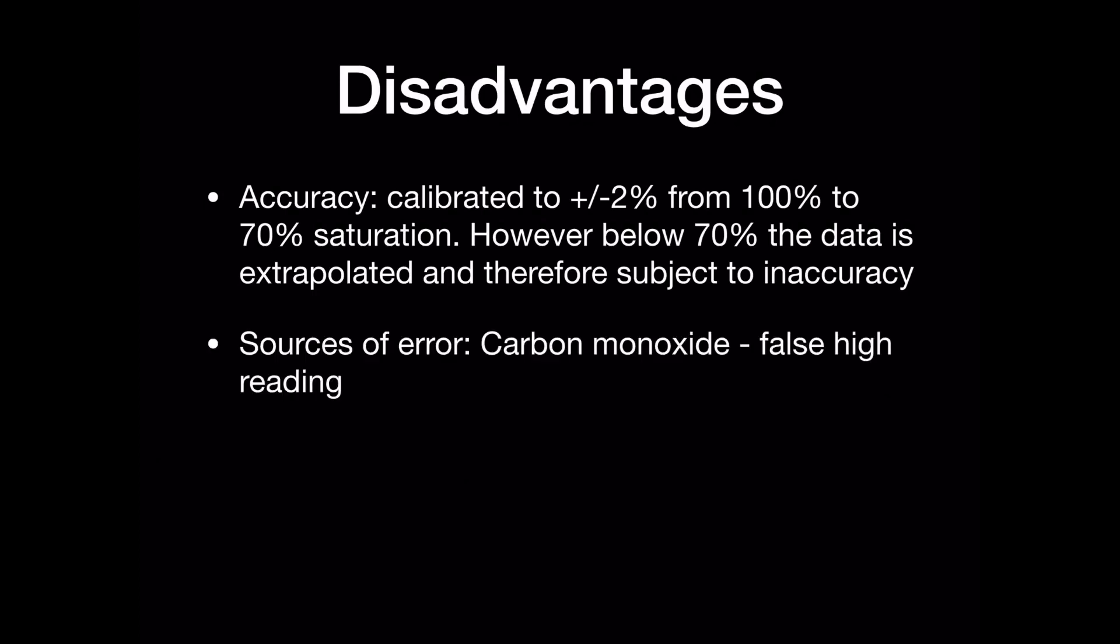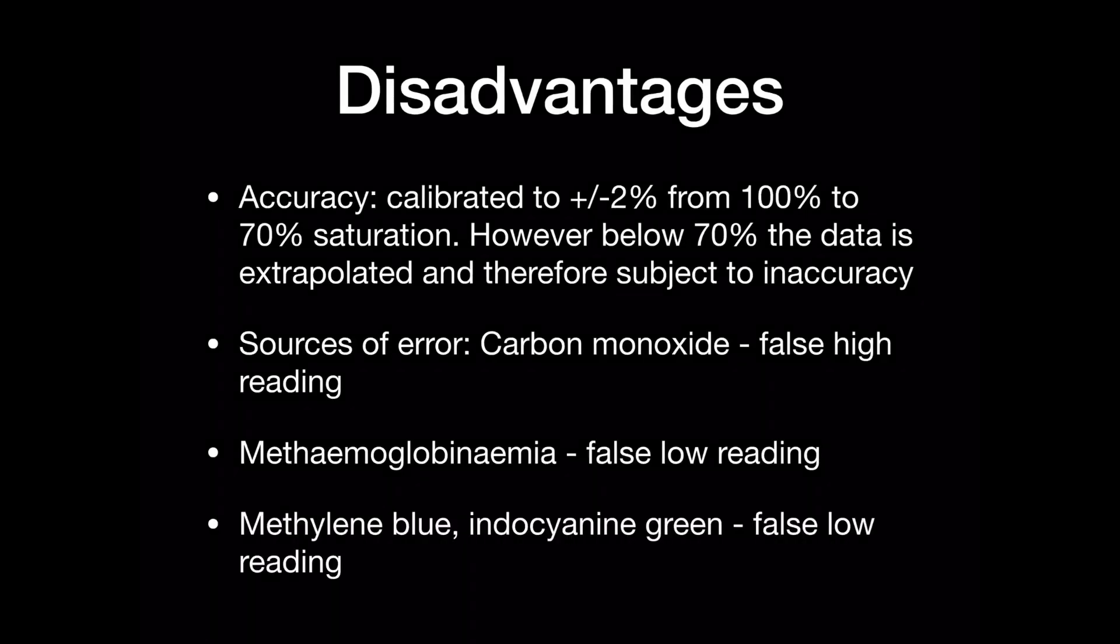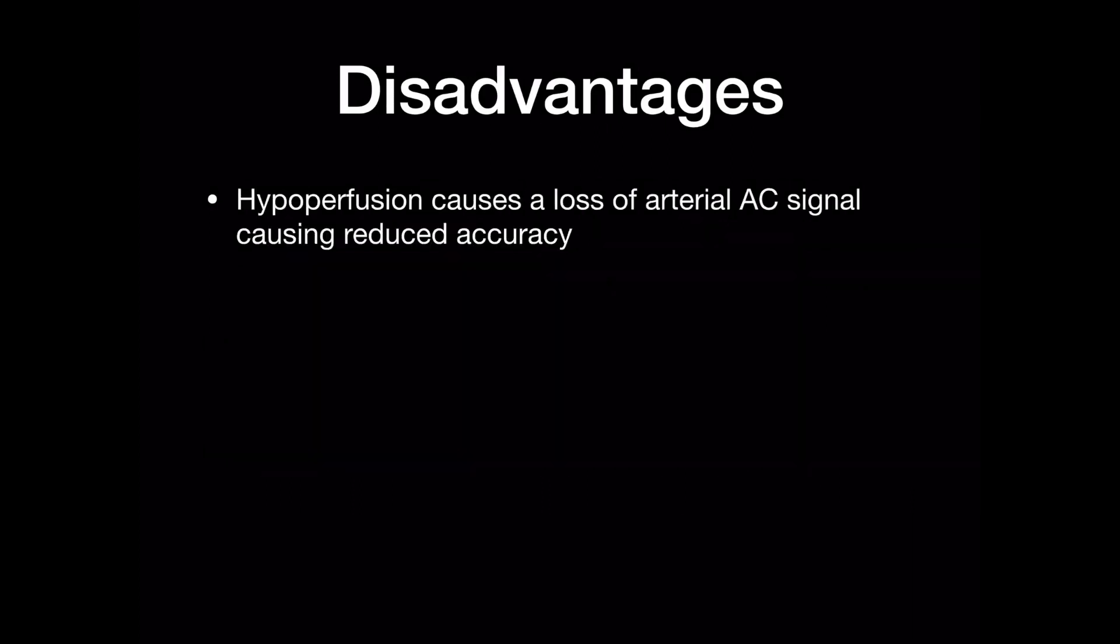There are a number of sources of error. Carbon monoxide causes a falsely high reading usually at 100%. Methemoglobinemia causes a false low reading usually around 85% and methylene blue and indocyanine green dyes also cause a false low reading.